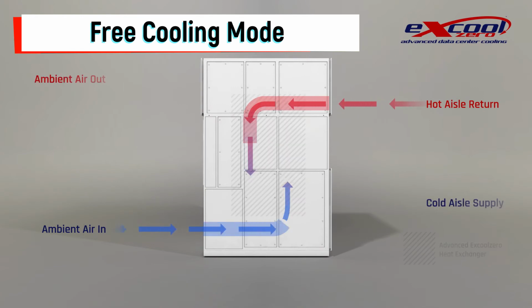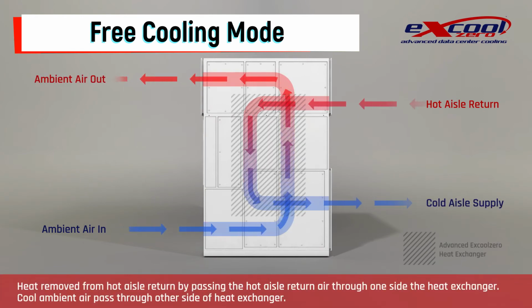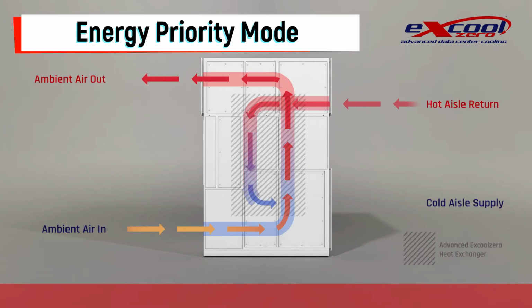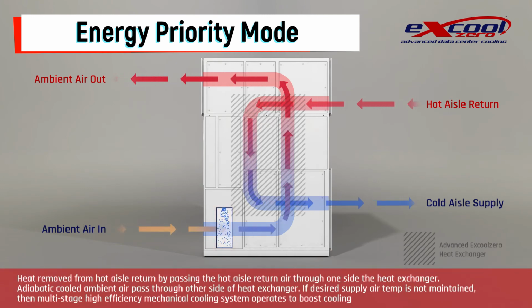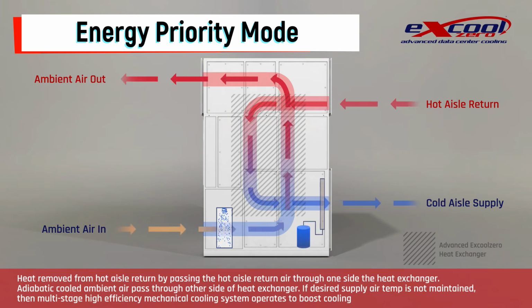Choosing a system with the flexibility of operation is critical for efficient operation of any cooling system for a data center. The operational modes need to be flexible in respect to climate conditions, cost of power, and cost of water. The Excool Zero system allows data center operators to manage their operations of their cooling systems with ease. The operator can either select the units to function in energy priority mode, where overall reduction in energy is prioritized. Alternatively, the operator can run the systems in water priority mode, where reducing the overall water consumption becomes the key driver.